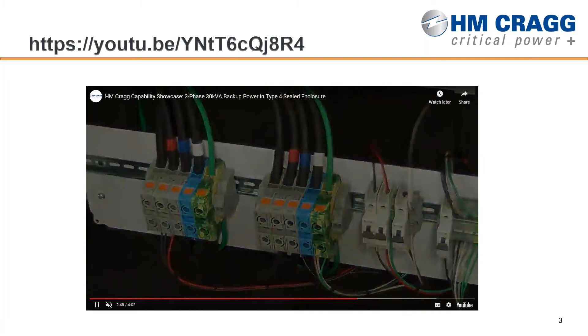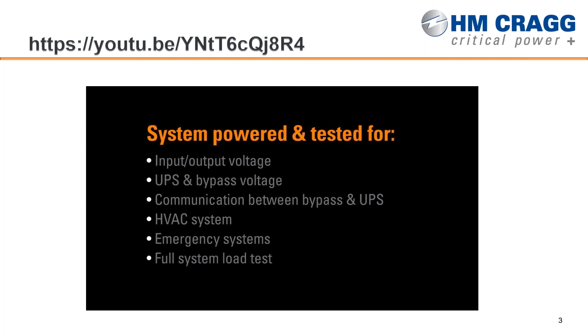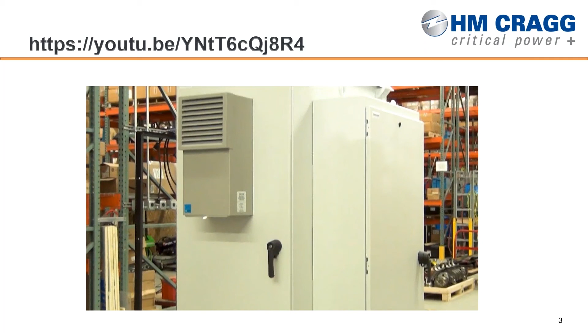Our hydrogen sensor system kicks on the vent kit at 1% hydrogen levels, and it will also output a warning alarm at 2% volume of hydrogen in the cabinet. That is a Modbus capable signal that pushes out to the user to get out there and take a look at the situation. We ship all of our integrated systems on shock pallets to minimize any shipping or freight damage on the way to the end user site.